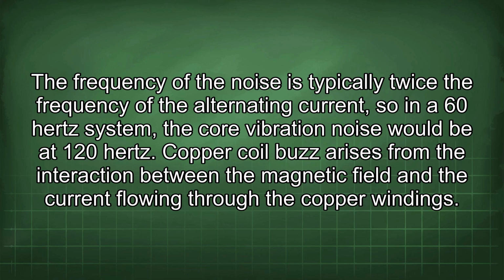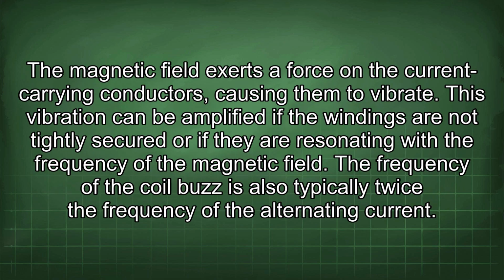Copper coil buzz arises from the interaction between the magnetic field and the current flowing through the copper windings. The magnetic field exerts a force on the current-carrying conductors, causing them to vibrate. This vibration can be amplified if the windings are not tightly secured or if they are resonating with the frequency of the magnetic field. The frequency of the coil buzz is also typically twice the frequency of the alternating current.